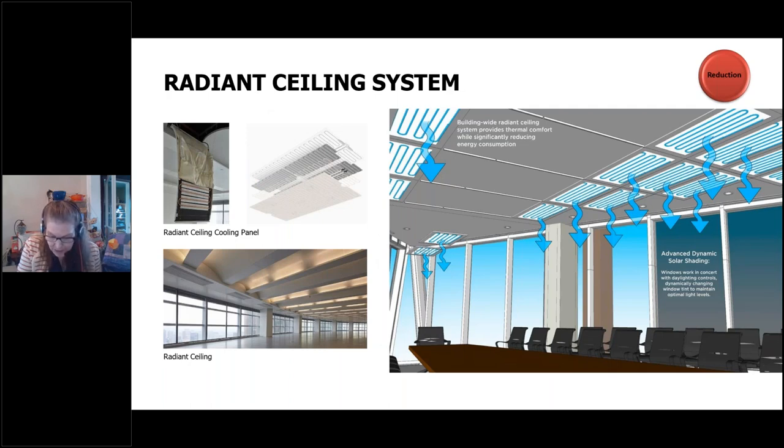The electrochromic windows help control radiant heat gains and complement the radiant cooling system, enabling a set point of 78 degrees inside while complying with the ASHRAE thermal comfort zone. In fact, we had a brownout during one of the hot days in 2019, and we ended up tinting the whole building to the darkest 0.08 solar heat gain coefficient tint. And I was really impressed at how well this combination of tight envelope and tinted windows worked while Pepco stabilized our grid. Next slide.